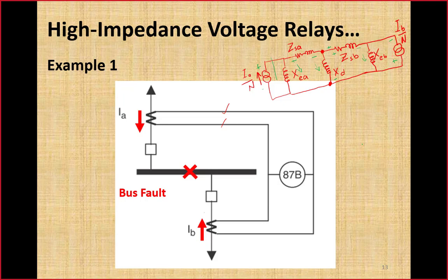So that will be same as the direction in circuit A. Now magnitude is also very high, and now this current is going to be forced to flow through this high impedance branch from two sides. Because direction is same, here current will flow in this magnetization branch, high impedance over voltage relay, and high impedance of this magnetization branch. So all these three impedances which would carry this high current are very high in magnitude.